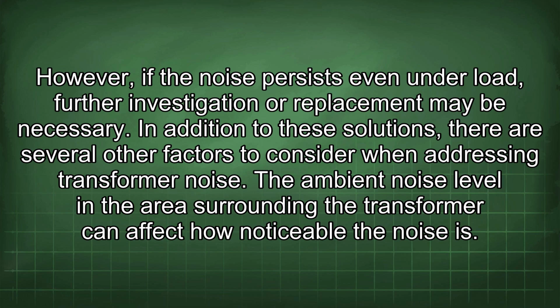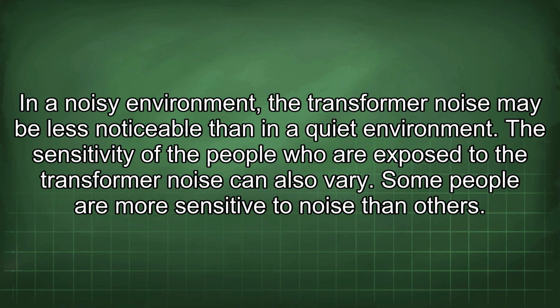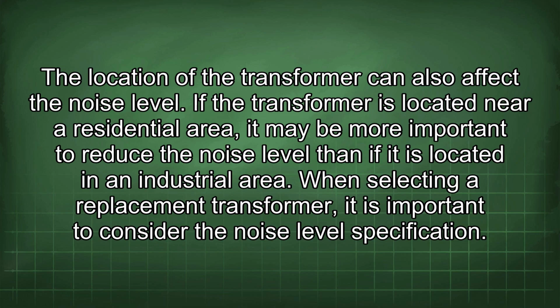In addition to these solutions, there are several other factors to consider when addressing transformer noise. The ambient noise level in the area surrounding the transformer can affect how noticeable the noise is. In a noisy environment, the transformer noise may be less noticeable than in a quiet environment. The sensitivity of the people who are exposed to the transformer noise can also vary. Some people are more sensitive to noise than others. The location of the transformer can also affect the noise level. If the transformer is located near a residential area, it may be more important to reduce the noise level than if it is located in an industrial area.